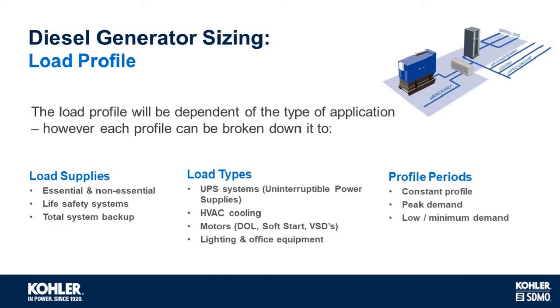So what are the load types? Well, is there a UPS part of the system? What are the heating, ventilation and air conditioning loads? And are there any large motors to start? And are they direct online or are they fitted with soft starts or variable speed drives? And is there lighting and office equipment that needs to be supported?